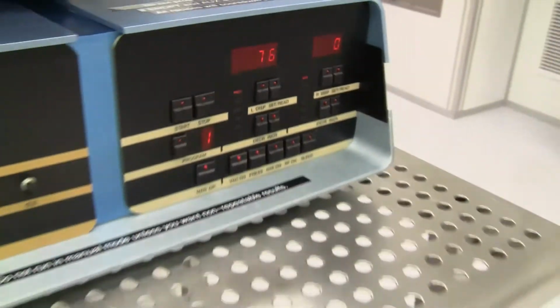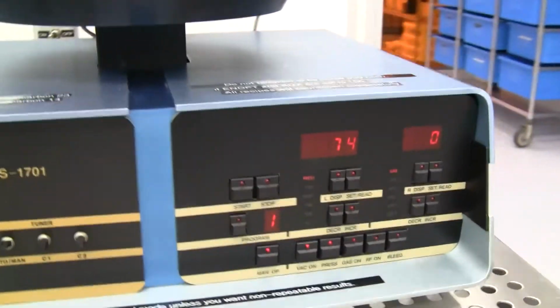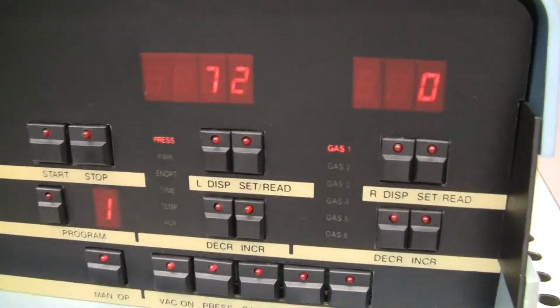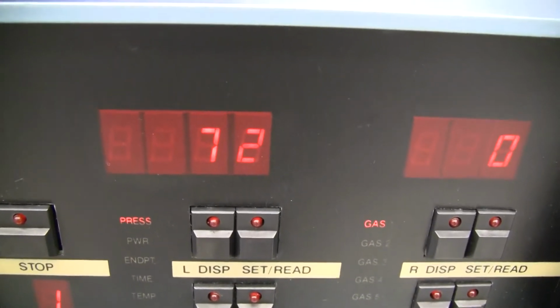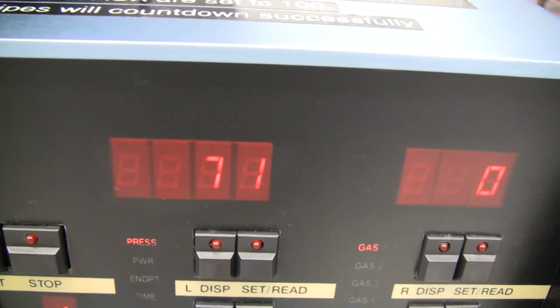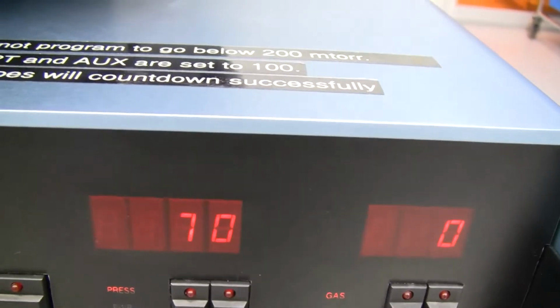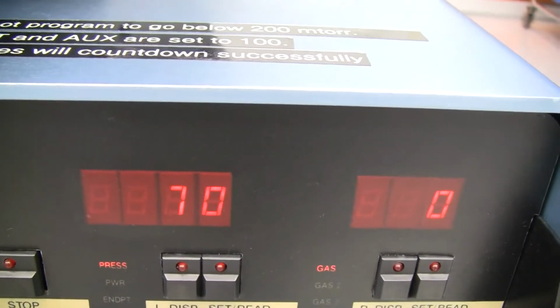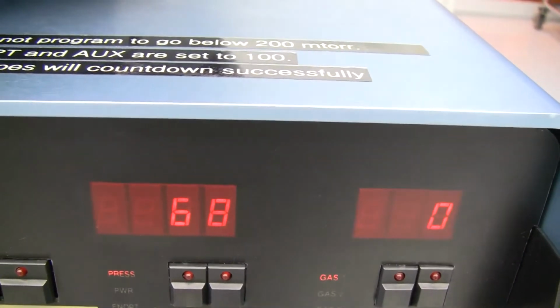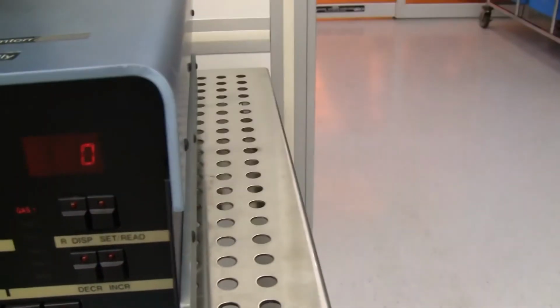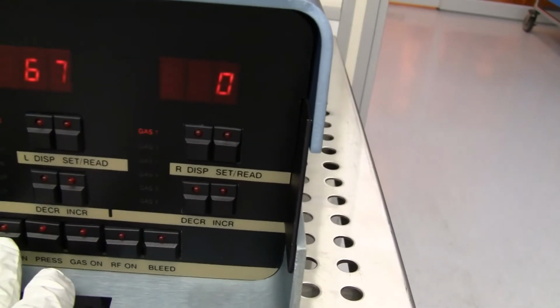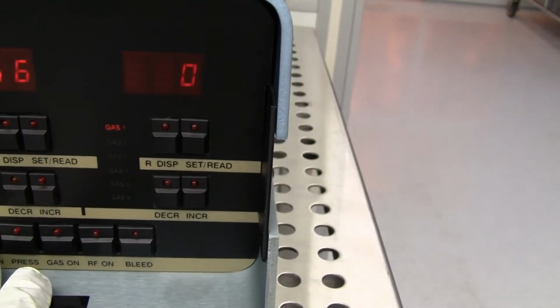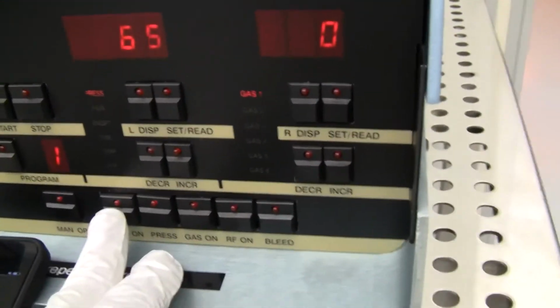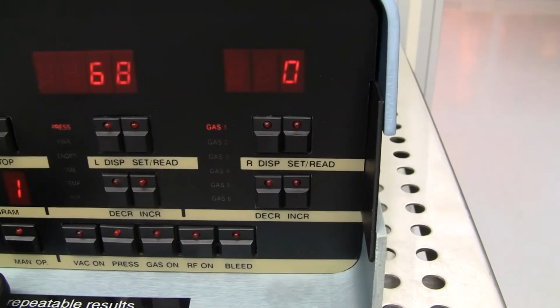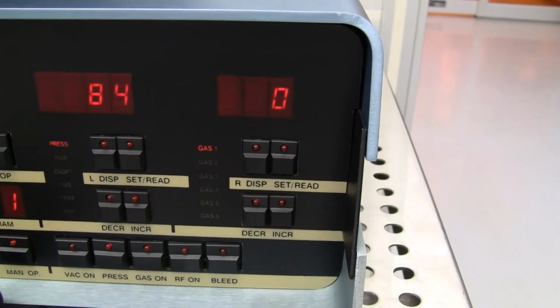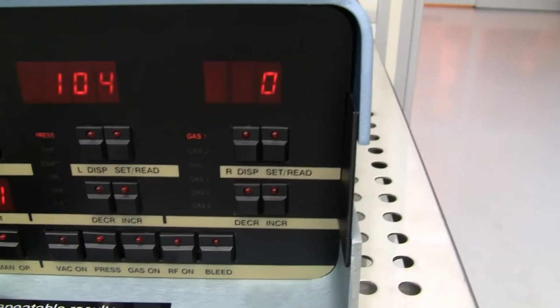Once it gets to 70, I will start a timer, turn off the pump and start a timer. So I'm going to turn off the vacuum, and that doesn't turn off the pump, it just isolates the chamber with a valve. And then once it gets back up to 70, then we'll start the stopwatch. Okay, and we're off. Let's see how long it takes to get to 100. Okay, 6 seconds to get to 100.